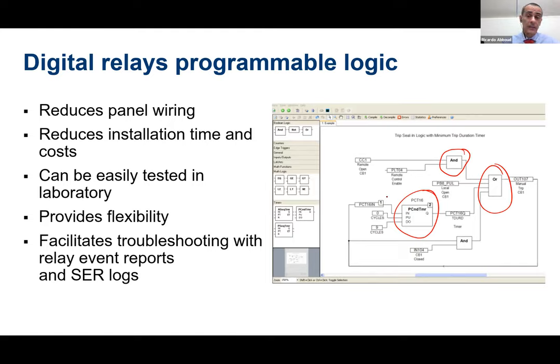So we can create special schemes, we can create new protection functions using the programmable logic that is available in the relay. So we can develop special control schemes very, very easily without increasing the number of wires that you have in the panel. So basically we are going to shrink the space that is necessary to install panels in the substation. Okay. So this will reduce panel wiring, reduce installation time and costs, and can be easily tested in the laboratory.